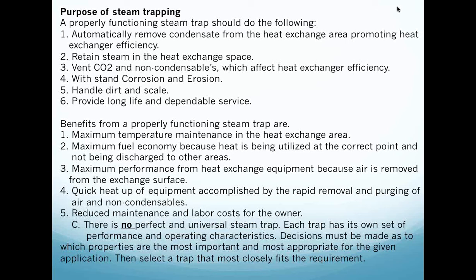A steam trap should provide long life and dependable service, and one of the things that I need you to know is that each of you has a responsibility with the steam traps that are in your facility, in your area. We become the guardians of these devices. They are built to do a great job, regardless of the color, the trap type. They would not be in your facility unless someone helped select the proper capacity and the proper technology. But we have to make sure that we do our job and that we help oversee these devices so that they get the opportunity to run to their maximum life.